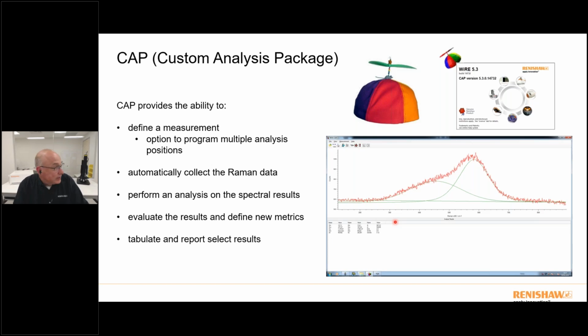So if you have ever used a Renishaw system, you may have seen within the Renishaw WiRE program group a program called CAP that has a little beanie with a propeller on it as the icon. I sometimes think the software guys have too much fun developing our icons, but this is the CAP software. CAP stands for Custom Analysis Package, and this is a package which allows you to automatically collect your data, so you can now define your measurement, what's gonna happen. You can have that with motorized positioning, so you can collect multiple data points, and as it collects the data, it's going to analyze the data by either background subtraction and curve fitting and other things like that.